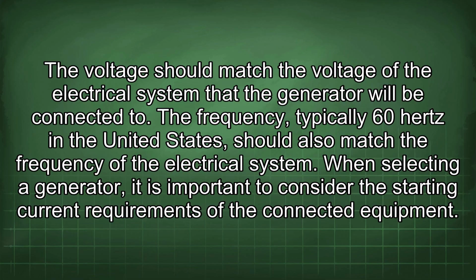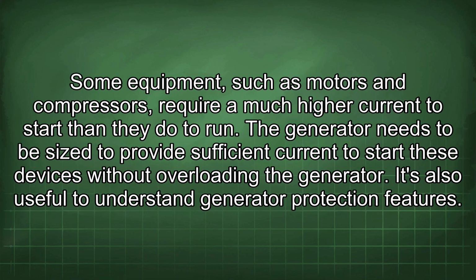When selecting a generator, it is important to consider the starting current requirements of the connected equipment. Some equipment, such as motors and compressors, require a much higher current to start than they do to run. The generator needs to be sized to provide sufficient current to start these devices without overloading the generator.